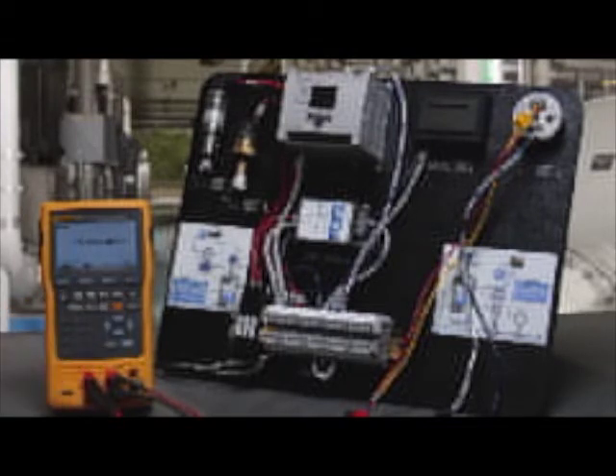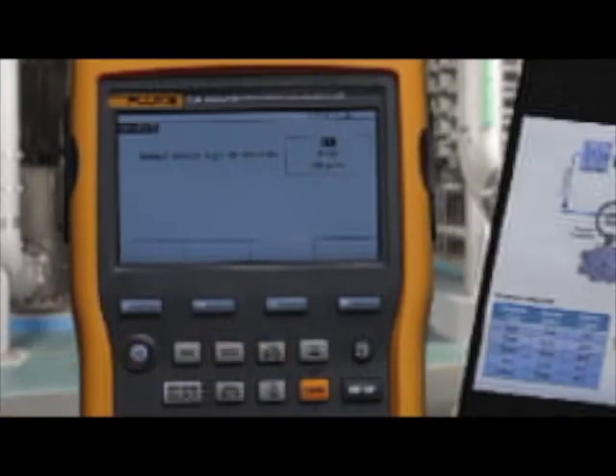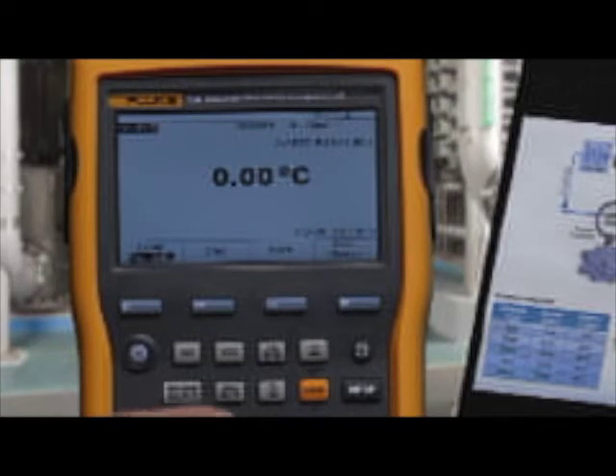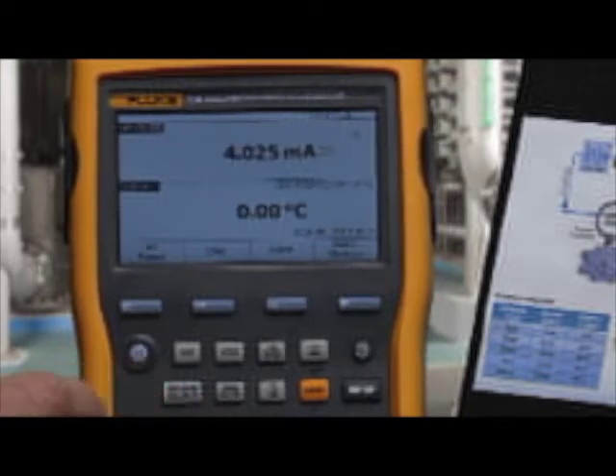Next we want to configure the input to the transmitter, the RTD source of the calibrator. Select thermocouple RTD and RTD, PT100, 385, input a temperature, and then move to the split screen to document the calibration.